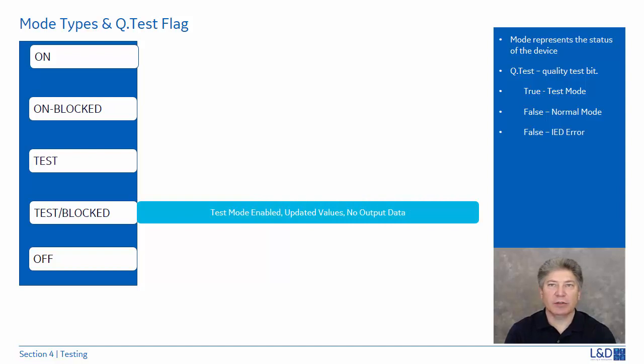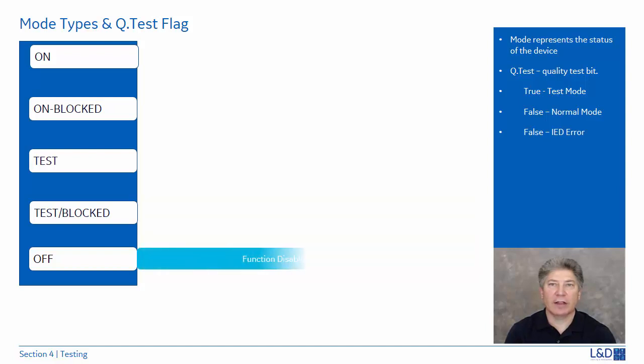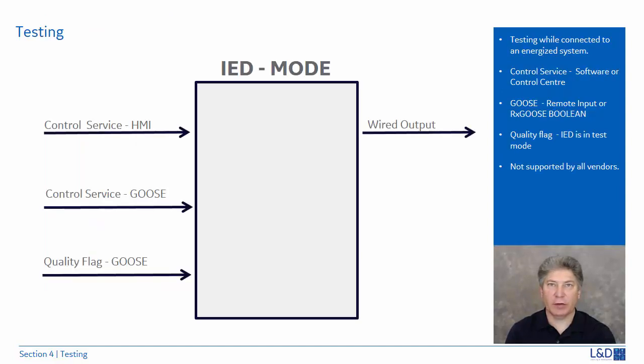This is where the test mode is enabled. We have updated values, but the output data is blocked. The Q.test is set to true. And finally, the last one is off, where the function is disabled, we have no outputs, and the Q.test bit is set to false. Methods for testing IEC 61850 system components in an energized substation remain available in Edition 1.